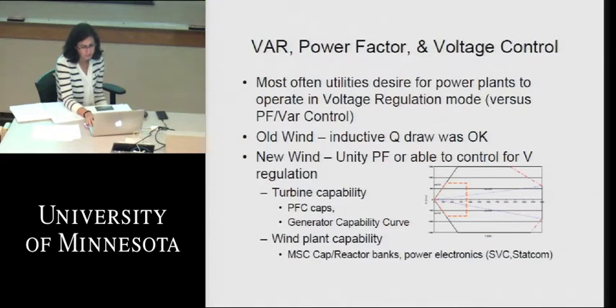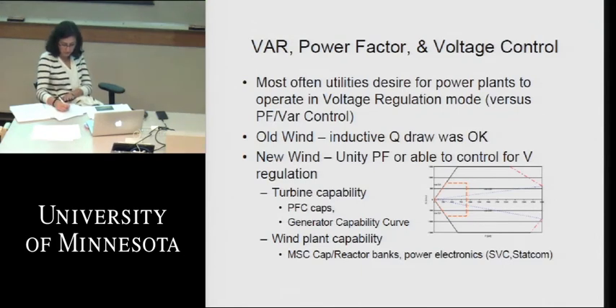So that's at the turbine level, but the requirements are always for the wind plant, because the wind plant is connecting up to the system. So we may have to put extra mechanically switched capacitors and reactors into the switchyard of the project, or power electronics, what I call FACTS devices here, a static VAR compensator or a STATCOM, to give us complete control of reactive power and active power out to the grid. That will supplement what the turbines may or may not be fully capable of providing to meet the interconnection requirements I alluded to earlier. Okay, next slide.